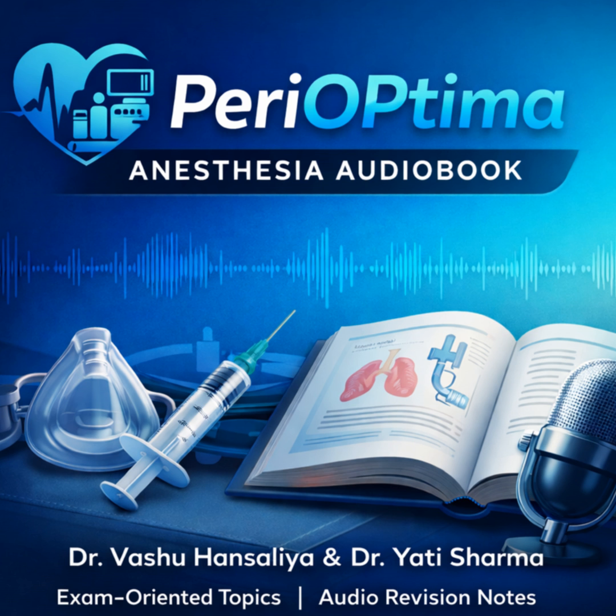Gas exchange occurs purely across the microporous membrane via diffusion gradients, oxygenating the hemoglobin and sweeping away the carbon dioxide. And the temperature control? Built directly into the oxygenator module is a heat exchanger. It consists of steel or aluminum tubes carrying hot or cold water. As the blood flows past the water tubes, the perfusionist can precisely cool the patient's core temperature down to 28 degrees, and then safely rewarm them back to 37 degrees before coming off the pump.